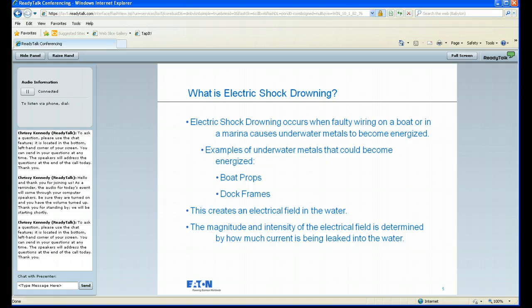Electric shock drowning occurs when there's some faulty wiring on a boat or within the marina that causes metals to be energized somewhere within the facility. Typically that's caused by some faulty wiring and an inadequate ground system that causes items such as boat props or dock frames to become electrified. While they become electrified, this leakage of electrical current enters the water and creates a gigantic electrical field, which you could have swimmers or people that simply fall off a dock enter in the water.